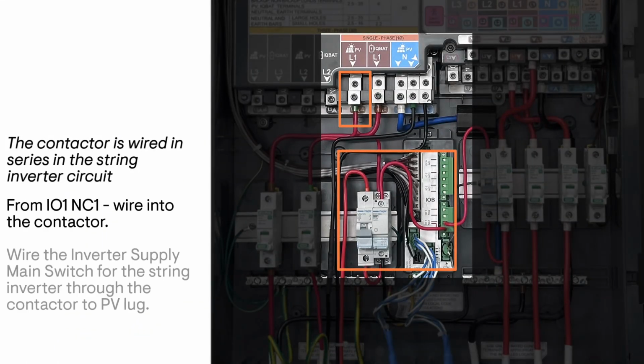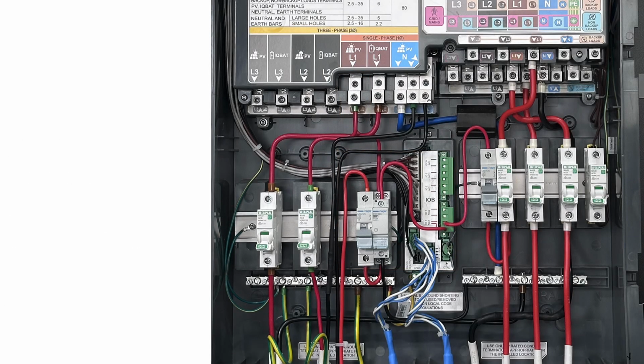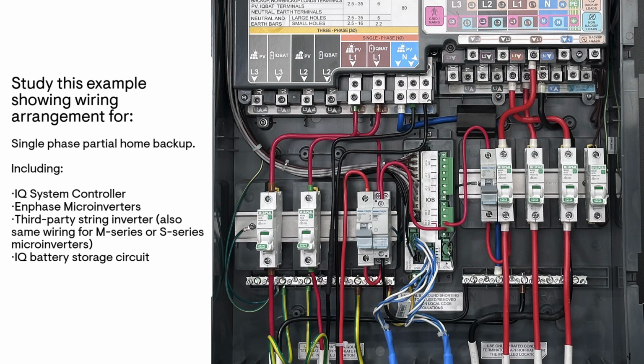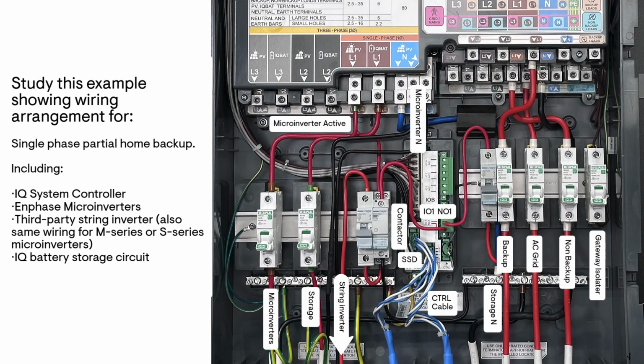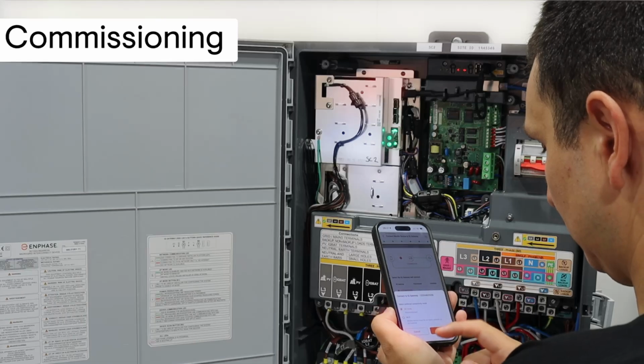From IO1 NC1, the contactor is wired in series with the string inverter supply circuit. The wiring passes through the contactor and then onto the inverter supply main switch, serving the string inverter. When reviewing your installation, carefully verify all circuit labels and wiring connections within the IQ system controller. Contactor wiring arrangements can be configured for either single-phase or three-phase solar installations. Always verify the specifications and terminal connections of the selected contactor before commissioning.